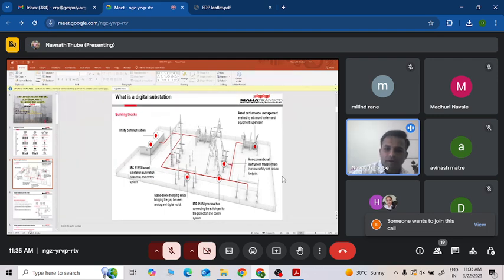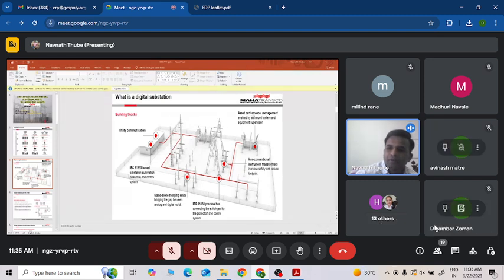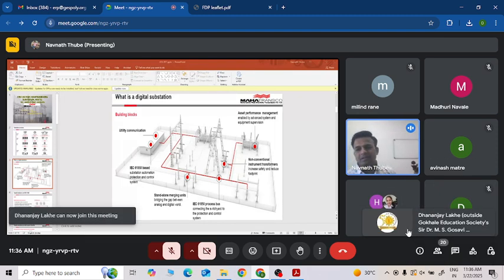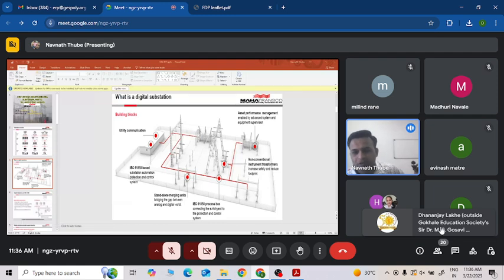The process interface box, PIB for short, is installed in the yard near the conventional equipment in the switchyard. In the PIB, all yard equipment like transformer, ICT, CT, PT, CB, isolator, etc., are connected with copper cable as per conventional practice. The SAM input output unit, metering unit, MFM and TCS relay are also connected in the PIB. It communicates between yard equipment and the control room IEDs and SCADA through fiber optic cable.